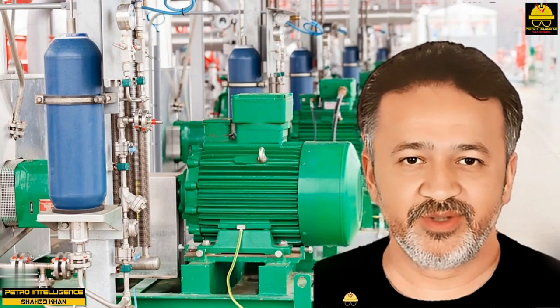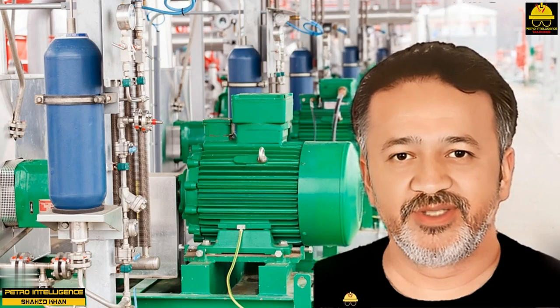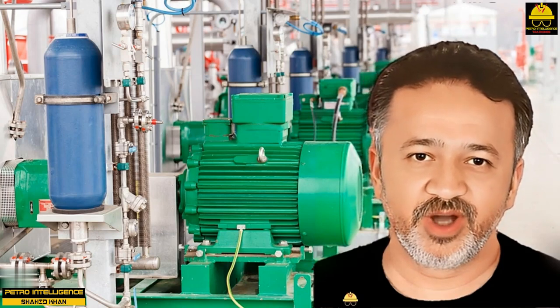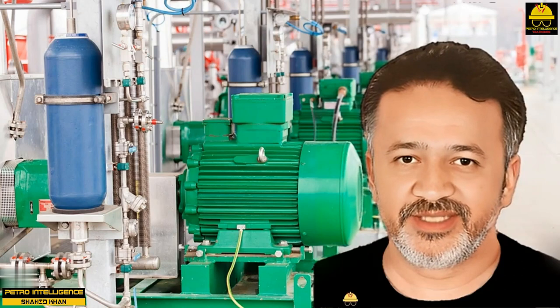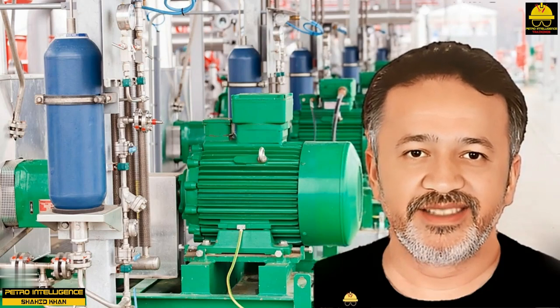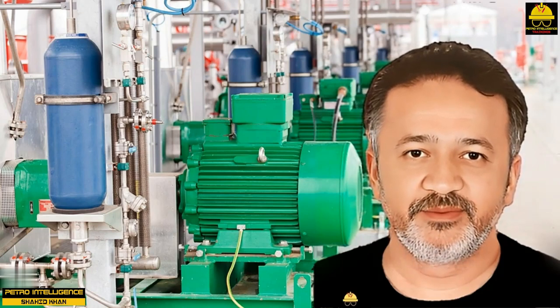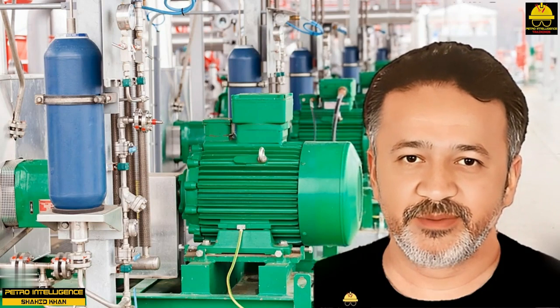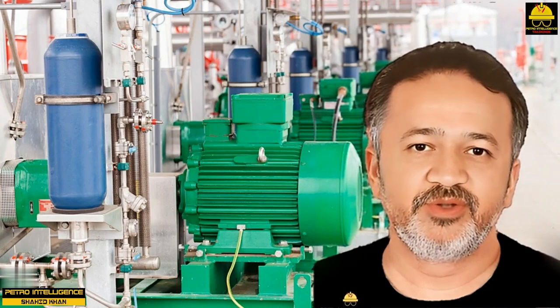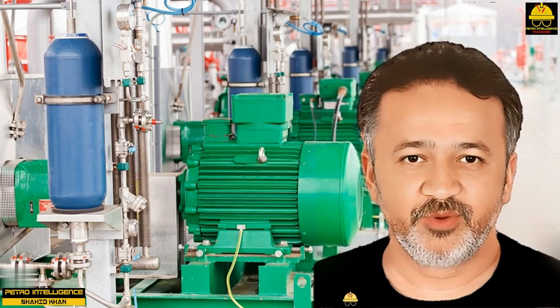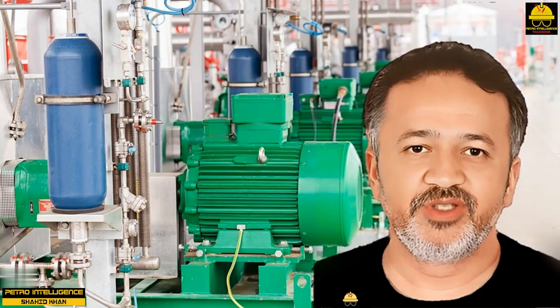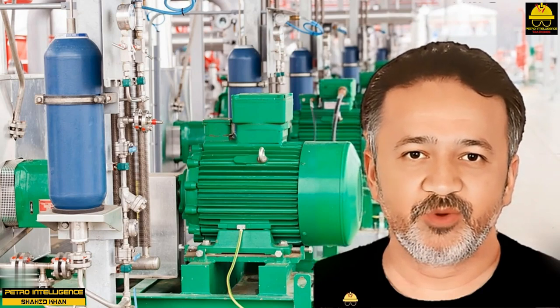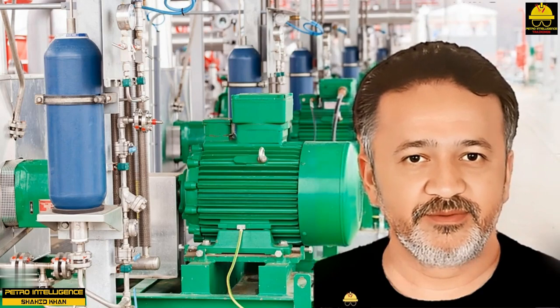Factors that affect suction head pressure are temperature, viscosity, a fluid's resistance to flow, level of liquid in the suction system, restriction in the suction line, and flow rate through the line. Solutions to insufficient NPSH are smaller horsepower, lower speed, lower NPSH requirements, larger diameter suction line, greater feed tank level or pressure, and cooler feed.